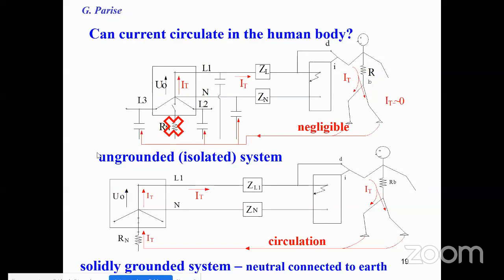Disconnect before. So can current effectively circulate in the human body? The circulation is generally negligible if the neutral point is not connected to the ground. And so for an isolated system, normally the expected prospective current value in the body is negligible. But if the system is connected to the ground or to the earth, that is, the neutral point is connected to the earth, the circulation is surely active. So you have to expect a danger.